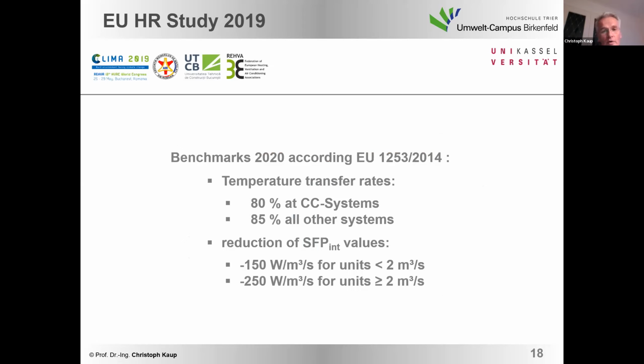So what we also did was taking into account the benchmarks which were written down already in the existing regulation, EU 1253, which was presented and published in 2014. And here we find temperature transfer rates of 85% for all kinds of systems, excepting the cyclic compound or run-around coil system with 80%, which is quite high.